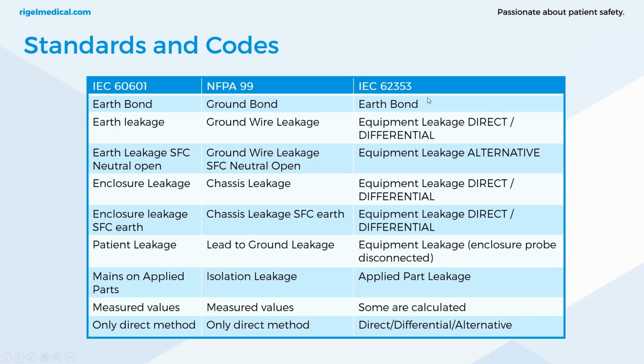Adhering to standards is best practice. It's good for being integral to good quality management systems. But NFPA 99 is something that's adopted in the USA, in North America, and is required by law. And the tests from all the other standards are based on IEC 60601. So you'll see here NFPA 99 uses this standard to derive its testing from. What it's effectively doing is simplifying those tests to make it easier for the end user.